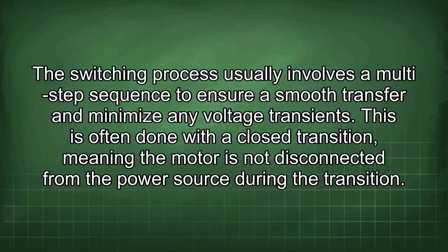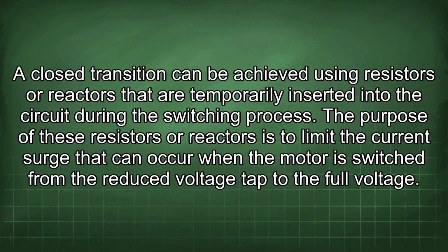This is often done with a closed transition, meaning the motor is not disconnected from the power source during the transition. A closed transition can be achieved using resistors or reactors that are temporarily inserted into the circuit during the switching process. The purpose of these resistors or reactors is to limit the current surge that can occur when the motor is switched from the reduced voltage tap to the full voltage.